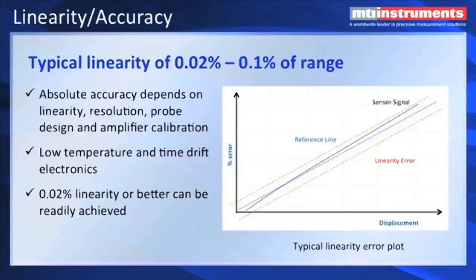One of the biggest accuracy issues related to capacitive displacement measurement is linearity. And if we look at the chart here, we can see a straight line, the blue line, that is very straight, and that's been curve fitted to the black line, which is the actual sensor response. And there's deviation about that blue line, and it's banded by the upper and lower red dotted lines, which would correspond to the linearity that we would see. So the absolute accuracy depends on the linearity and the resolution of the probe, and also the extra errors contributed by the amplifier. We also have very low temperature and time drift electronics, and we can achieve 0.02% linearity or better.